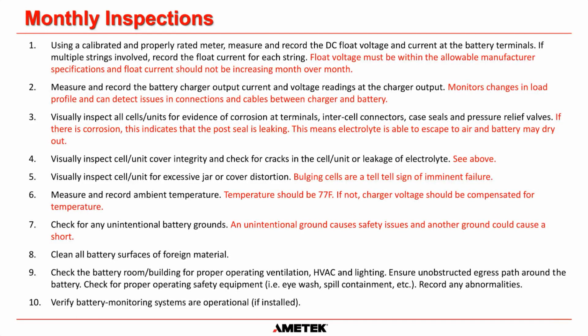Bulging cells are a telltale sign that that battery is going to fail, and it's going to fail very, very soon if it hasn't done so already. It means for some reason the gas inside that battery is excessive. That means it's probably been overcharged and it's going into thermal runaway, and it is not a good sign. They should be square in nature. They should not look like a football, for sure.